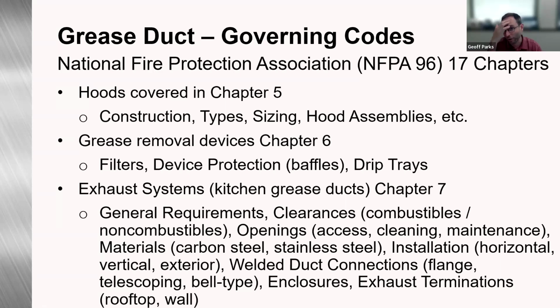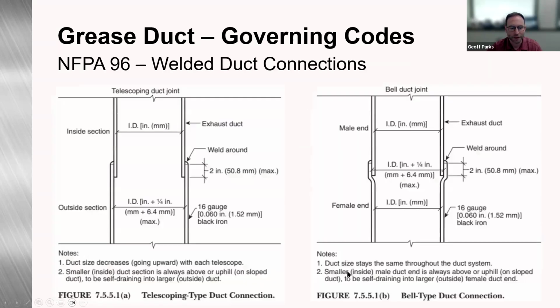One thing I do want to point out, if you notice, the IMC duct connections had butt weld, but NFPA does not have a butt welded joint type. So it would only be a flange, telescoping, or bell type. And out of NFPA, here's a couple of figures for the different types. You have your telescoping type duct connection, the bell type duct connection gives you minimum overlaps and ID, OD things.